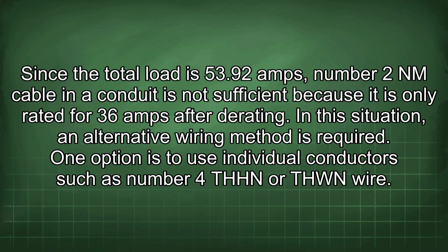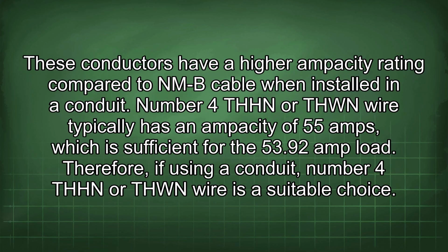In this situation, an alternative wiring method is required. One option is to use individual conductors such as number 4 THHN or THWN wire. These conductors have a higher ampacity rating compared to NM cable when installed in a conduit. Number 4 THHN or THWN wire typically has an ampacity of 55 amps, which is sufficient for the 53.92 amp load. Therefore, if using a conduit, number 4 THHN or THWN wire is a suitable choice.